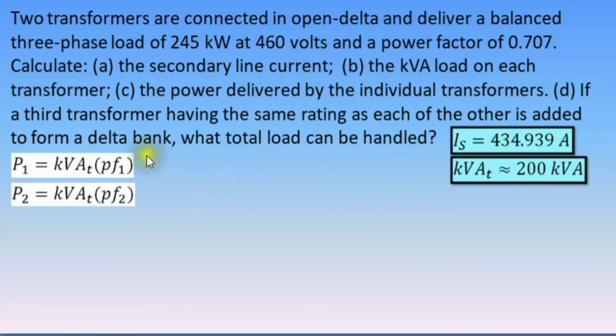To solve that, we have these formulas. The kVA on each transformer are the same, that is 200 kVA. But the power factors at which they will operate are different. Again, these formulas are derived from the formula of the real power, which is equal to the apparent power times power factor. But anyway, before we can compute the real power being delivered by each transformer, we first need to determine their power factors.